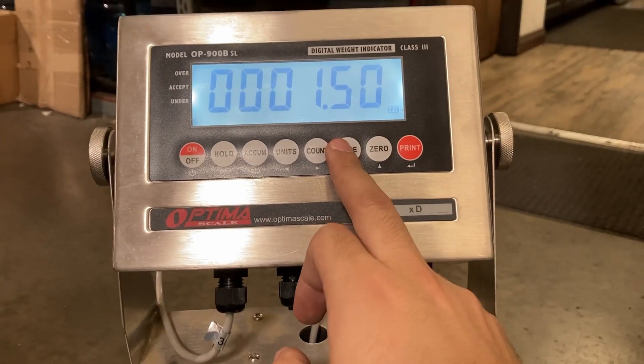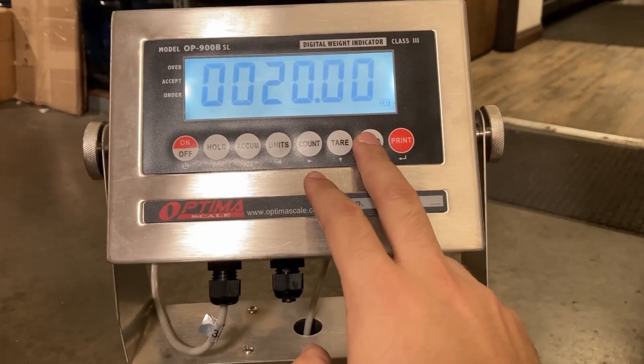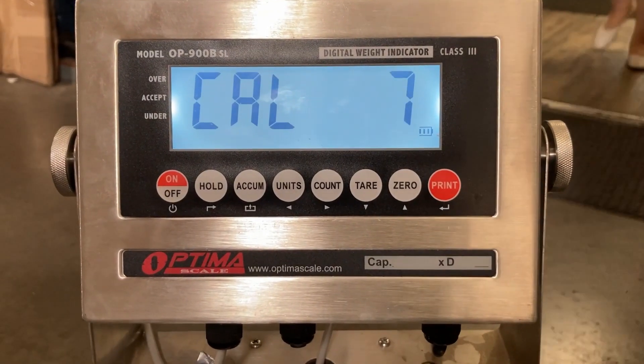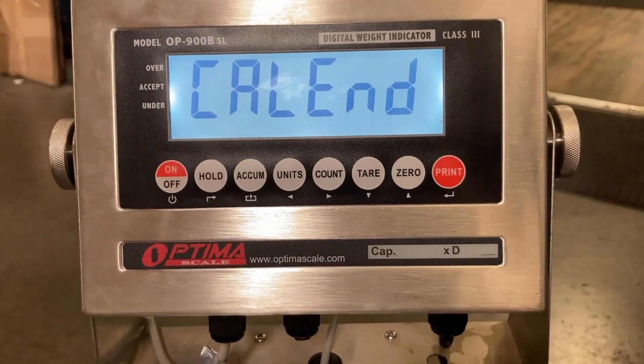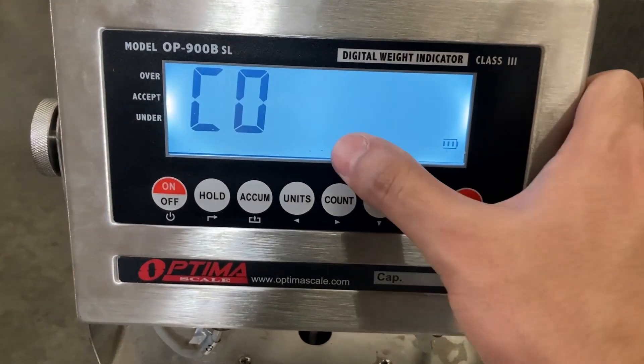Now use 50 pounds as the span calibration weight. Input 50 pounds — 50.00 — then place the 50-pound weight on the scale and press Print. Go to C07 and press the ACCUM button to save and exit.